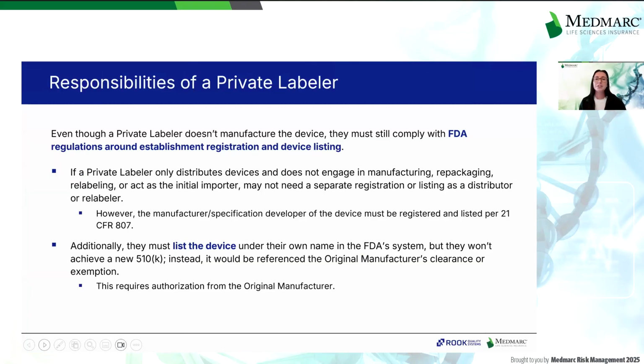Even though a private labeler does not manufacture medical devices, they may still have responsibility under FDA regulations depending on their role. If a private labeler solely distributes devices without engaging in manufacturing, repackaging, relabeling, specification development, or acting as the initial importer, they are not generally required to register their establishment or list the device under 21 CFR 807. However, if the device is marketed under the private labeler's own name or trade name, the device must be listed in the FDA's database under that name.